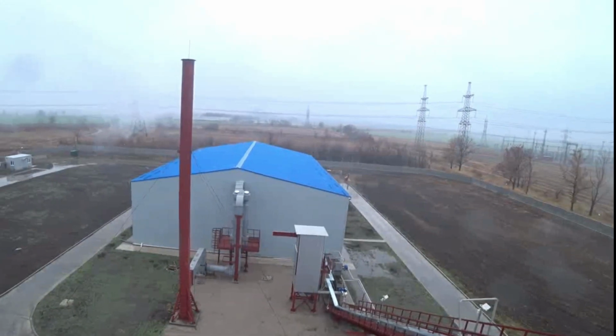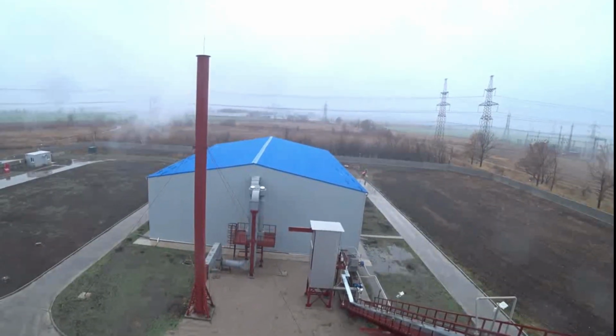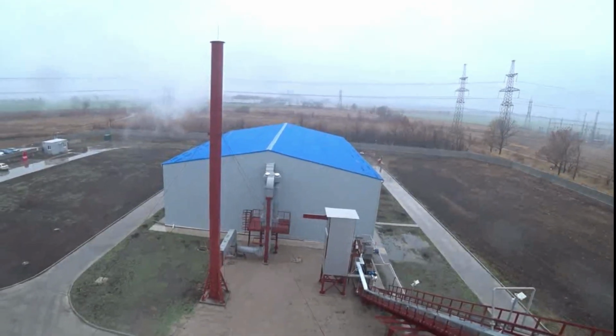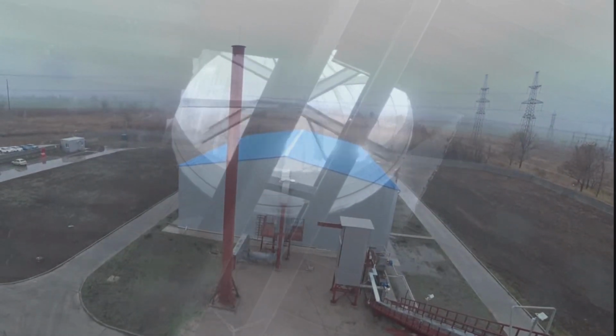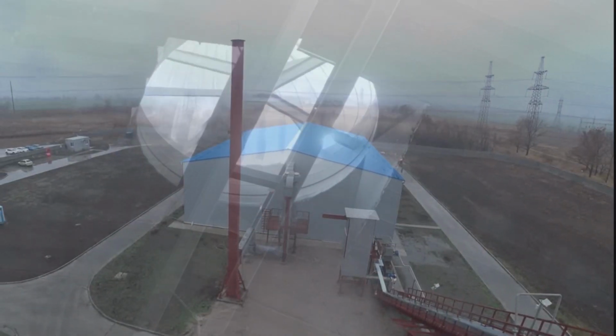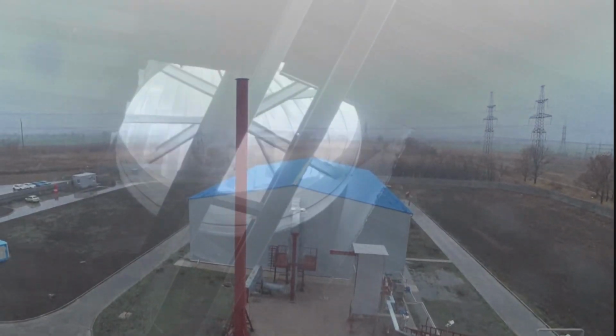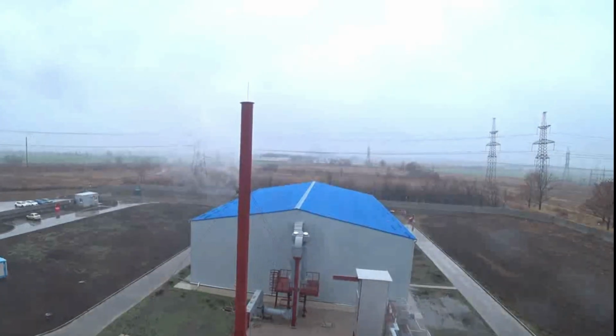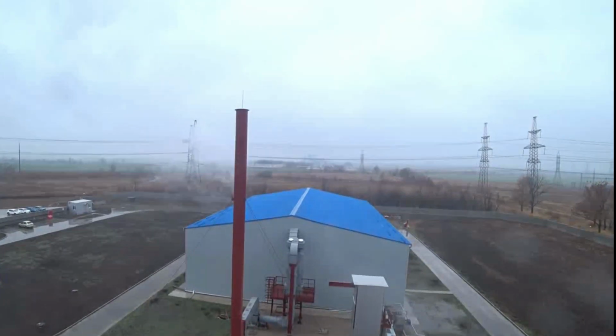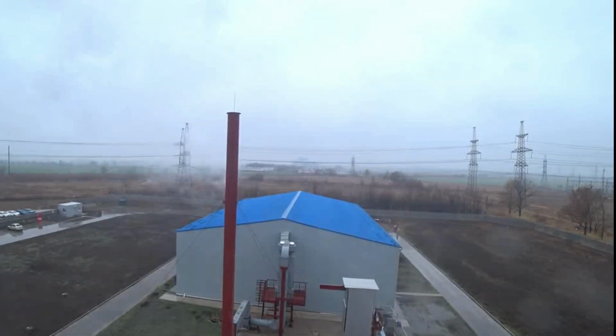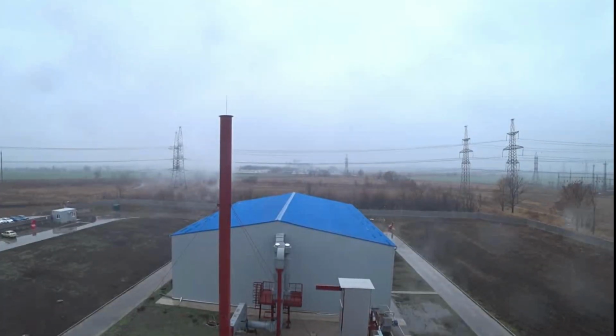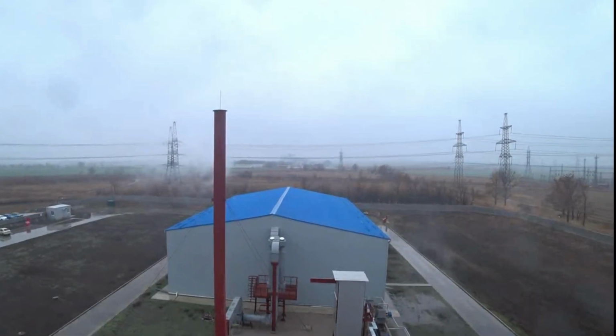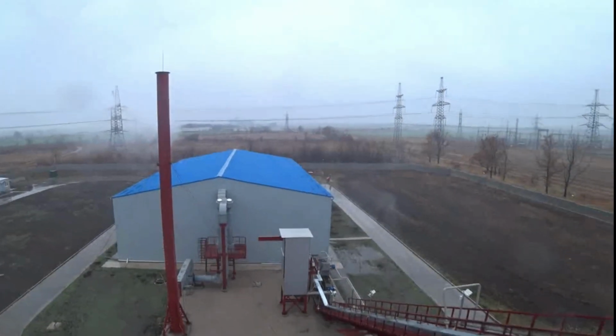The project provides for the creation of a vacuum inside the warehouse. The exhaust system operates continuously, while the condition of at least 1.5-fold air exchange of the room must be met. In front of the warehouse, you can see a high exhaust pipe, 20 meters high.